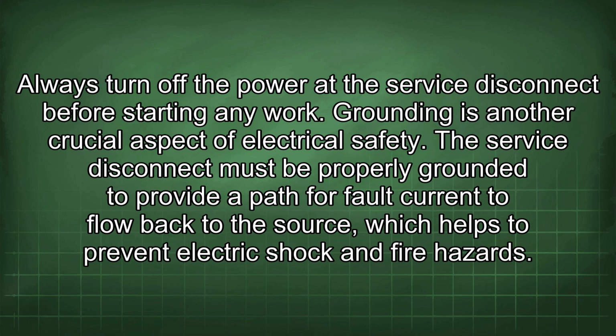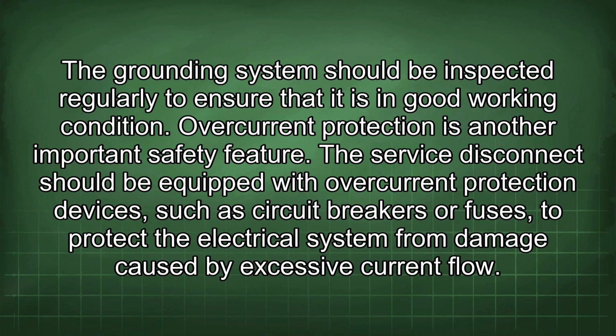Grounding is another crucial aspect of electrical safety. The service disconnect must be properly grounded to provide a path for fault current to flow back to the source, which helps to prevent electric shock and fire hazards. The grounding system should be inspected regularly to ensure that it is in good working condition.